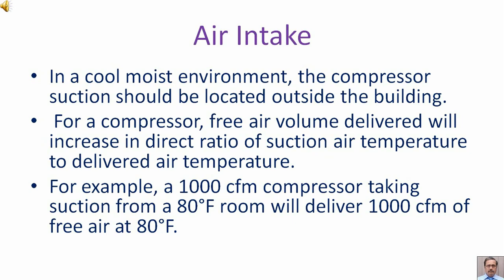In a cool, moist environment, the compressor suction should be located outside the building. For a compressor, free air volume delivered will increase in direct ratio of suction air temperature to delivered air temperature. For example, a 1000 CFM compressor taking suction from an 80°F room will deliver 1000 CFM of free air at 80°F.